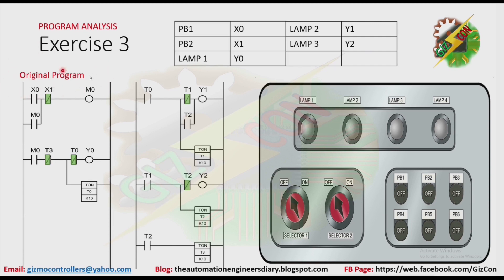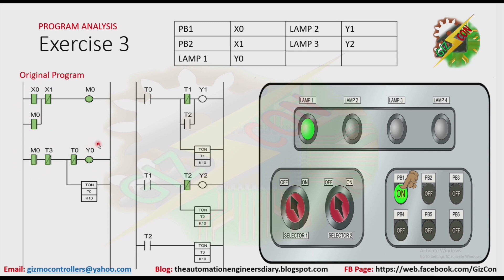Now let's press PB1. As you can see here, because X0 is energized, M0 will turn on. Because there is latching here, M0 will not turn off even if X0 is not energized anymore. Because M0 is on, that will make Y0 to turn on. And as you can see here, T0 will be activated after one second.